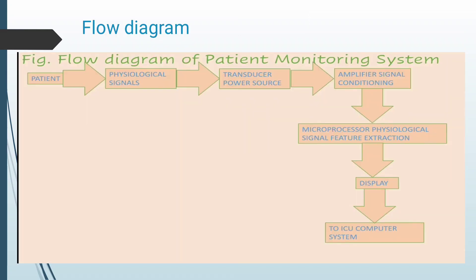Flow diagram: The system collects physiological signals from the patient. Using a transducer, it converts mechanical signals into electrical signals. It then amplifies the signal using an amplifier for signal conditioning. Using the microprocessor, physiological signal feature extraction is performed to extract the output, which is displayed on a display unit and also sent to the ICU computer system.